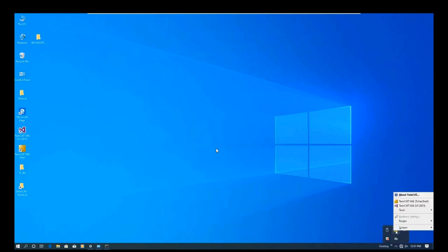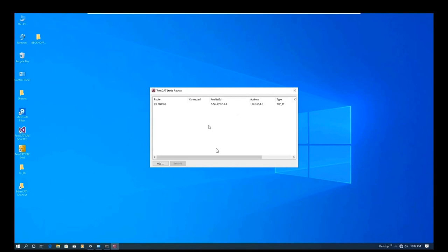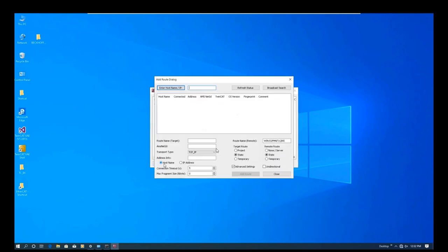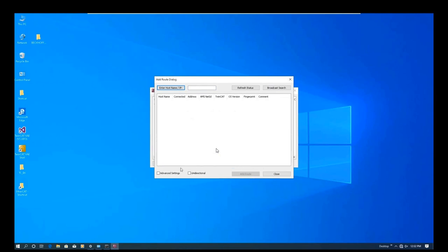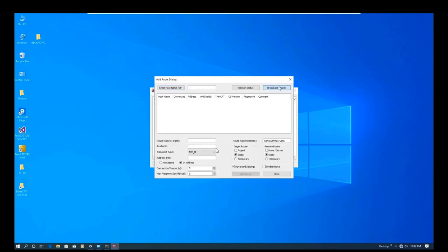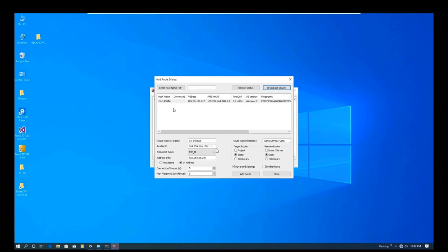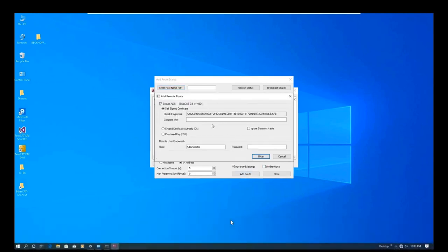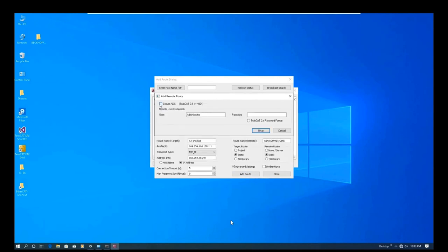From the system tray in the right corner, we switch to the TwinCAT router. After you install TwinCAT3, you will see this icon. We click 'Add' and then 'Broadcast Search'. We switch to IP address, select static, and don't forget to check the advanced settings. Click 'Search'. The router software scans and finds the controller. The virtual machine is connected. We disable the security — the default password is '1'.